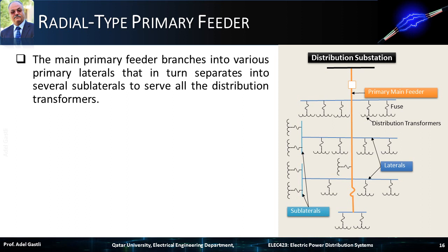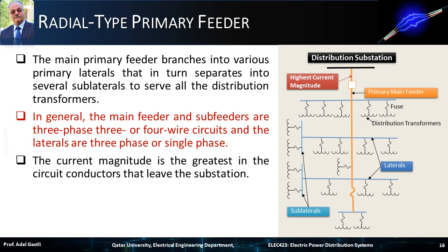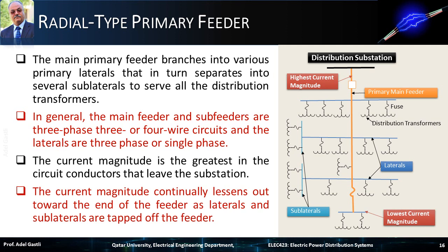As seen in the previous chapter and as shown in this figure, the main primary feeder branches into various primary laterals that in turn separate into several sublaterals to serve all the distribution transformers. In general, the main feeder and sub feeders are three-phase three or four-wire circuits, and the laterals are three-phase or single-phase circuits. It is clear that the current magnitude is the greatest in the circuit conductors that leave the substation and carry the total load, and the current magnitude continually lessens toward the end of the feeder as laterals and sublaterals are tapped off.